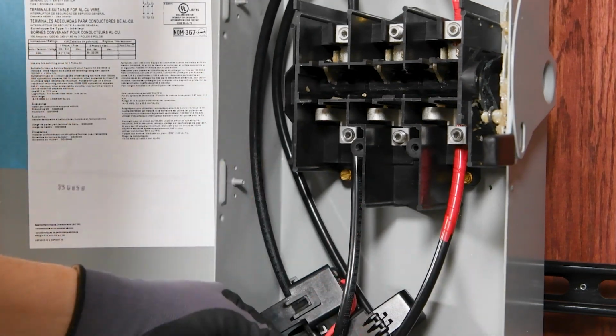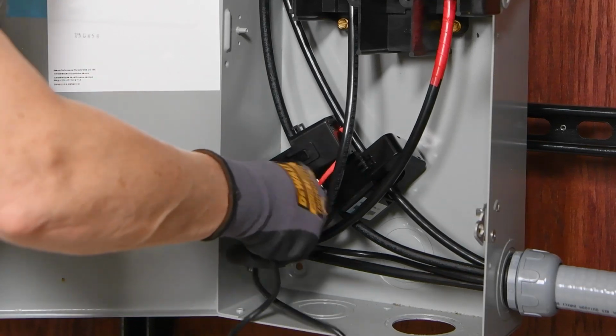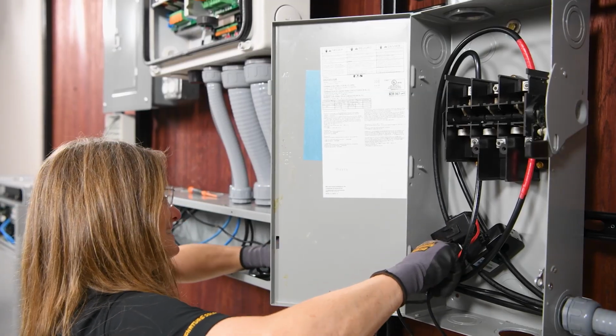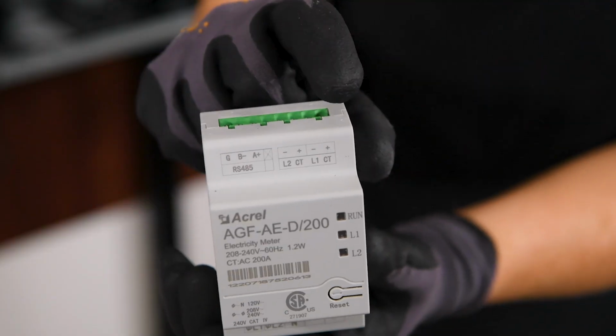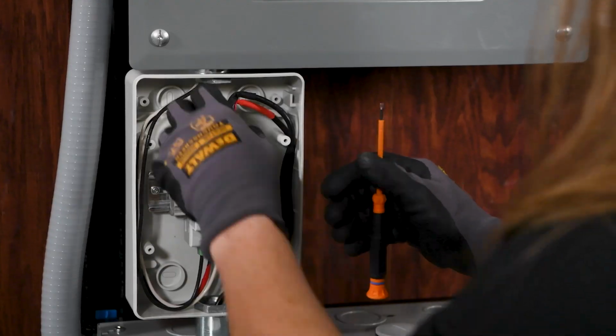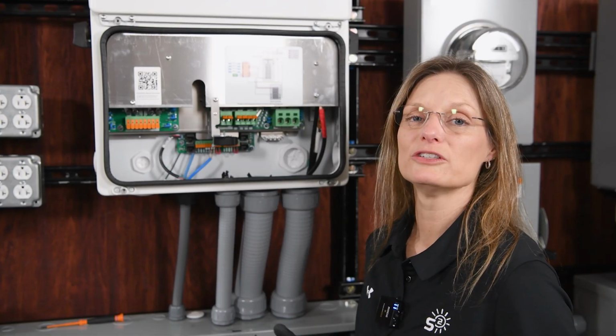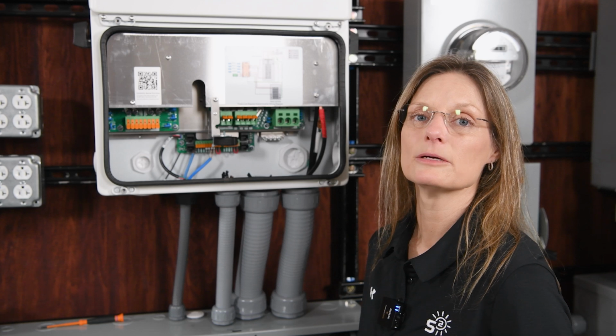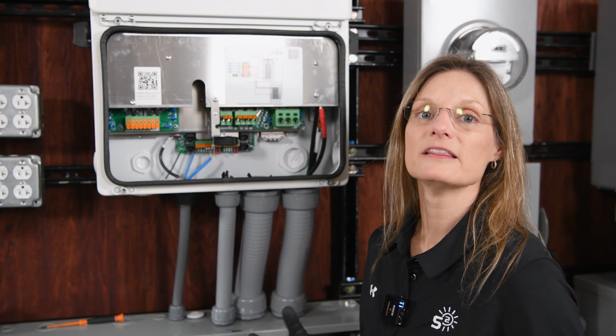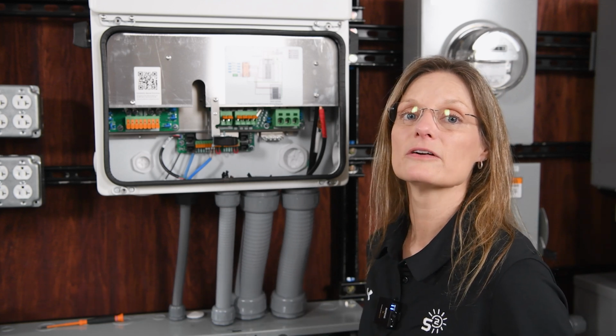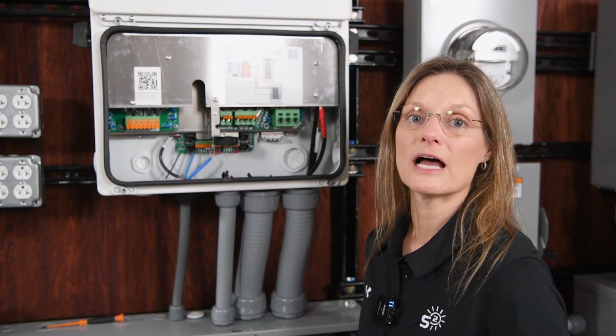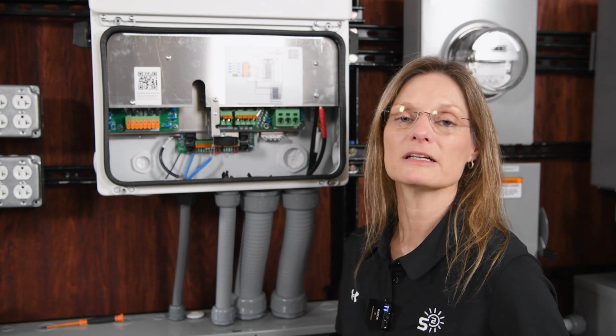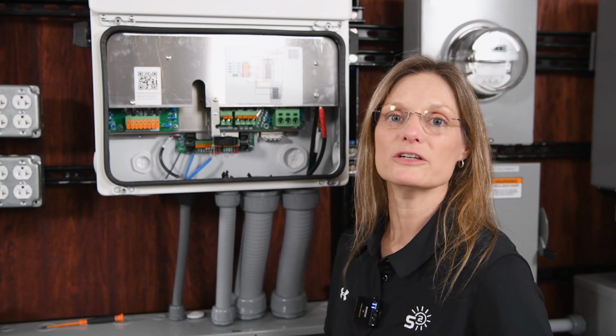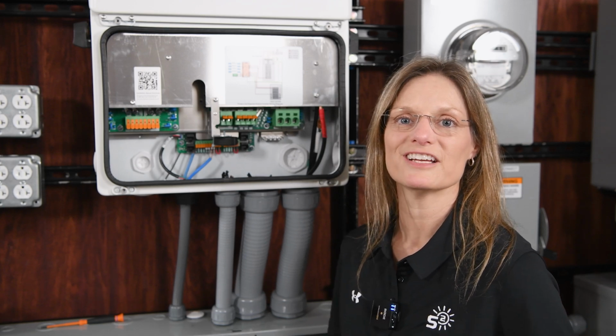lock closed. And then you will run your wire through your conduit, and this will connect into your AC meter where you see line 1 and line 2 in the correct inputs. As you move across your communications board, you'll notice there's some inputs for dry contact. That allows you to connect a generator up to your inverter to allow it, based on your settings, to automatically give power to your inverter and to your loads at certain times based on your settings.